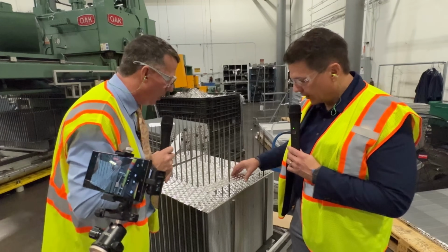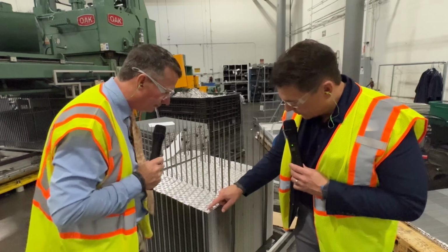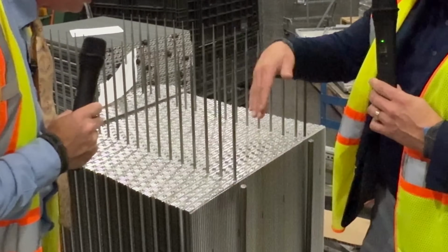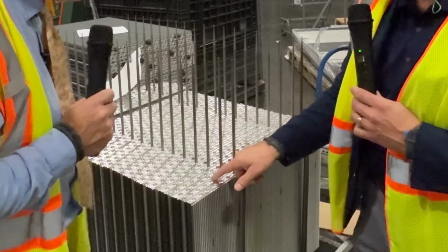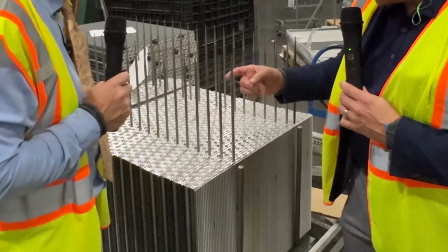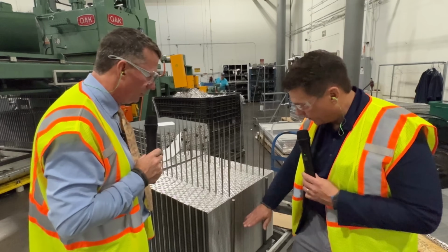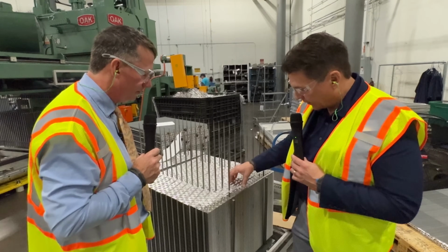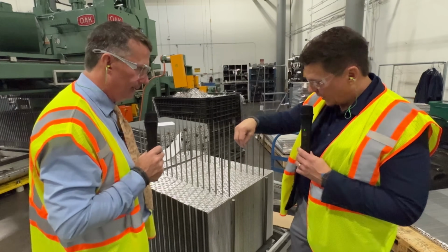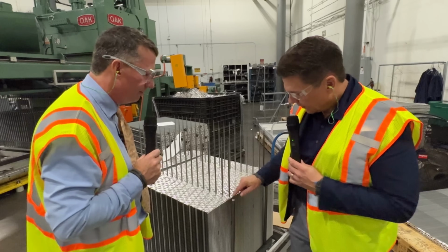Absolutely. The copper tubes we just looked at go through these holes, and you can see the little aluminum collar here. A divot. Yeah, but those fin patterns and waves, there's a lot of heat transfer engineering in those. Basically, just like these metal tubes that we're seeing holding this, those copper tubes will go through that, and they'll line up this fin deck. Then they'll put the tube through there and expand the bullet that we just looked at inside of that copper tube, and that collar height that you see here is very critical.